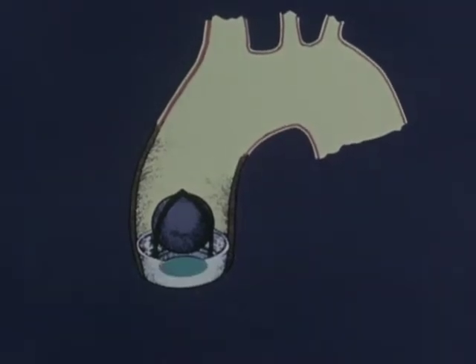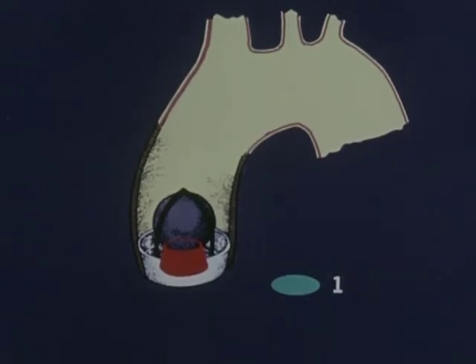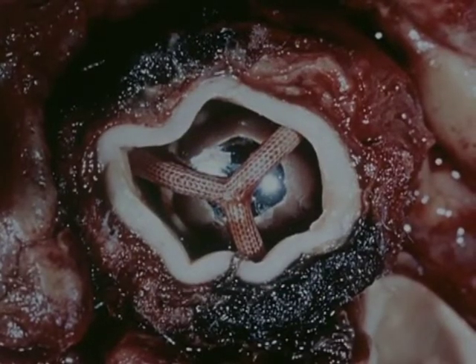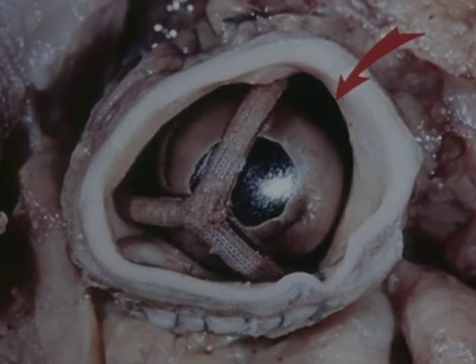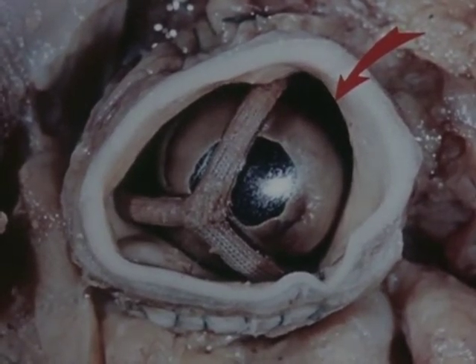The primary orifice represents the area of the inflow orifice at the seat of the valve. The secondary orifice is encountered when the ball is fully open and represents the area — a truncated cone — between the ball and the valve seat. The tertiary orifice represents the area between the diameter of the ball and the surrounding tissue, be it aorta or ventricular cavity. Examples of aortic valves with tertiary orifice obstruction are shown, viewed from above through sectioned aorta, where the area between the open ball and the aortic wall is too small, causing significant obstruction to forward flow.